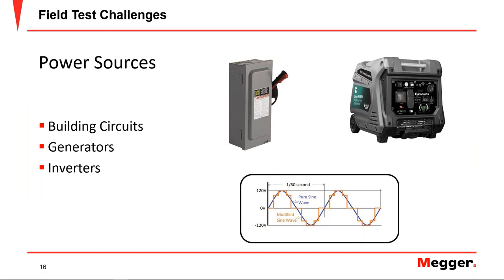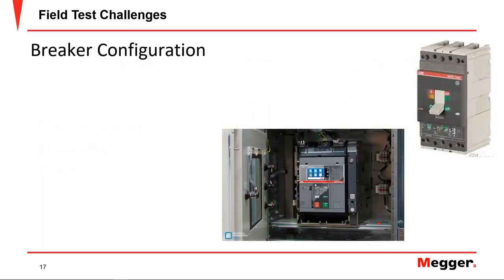Here we have to be really careful. The quality of the output of the generator or the inverter will affect the quality of the output of the SPI. We also need to make sure that we have enough power from either a generator or an inverter to comply with the specifications of the SPI 225. So that's the power. Then we need to look at the breaker configuration. Again, we're focusing on low voltage circuit breakers, not on power circuit breakers, which is more important, but not to be overlooked. First of all, the connection method, whether it is top feed or bottom feed.